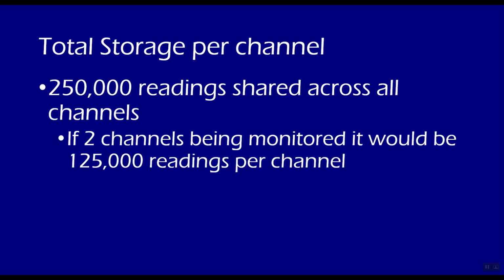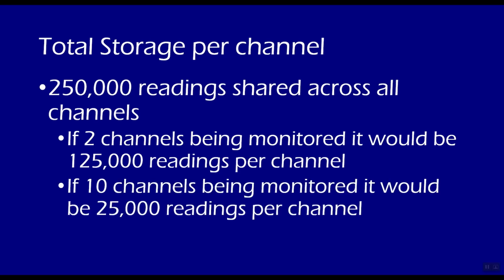The EL005 data logger can store up to 250,000 readings, which is shared across all the channels. So if, for example, you had 2 temperatures that you're monitoring, this would be shared across them. So you'd have 125,000 readings for each channel. And if you had 10 channels, it would be 25,000 readings.